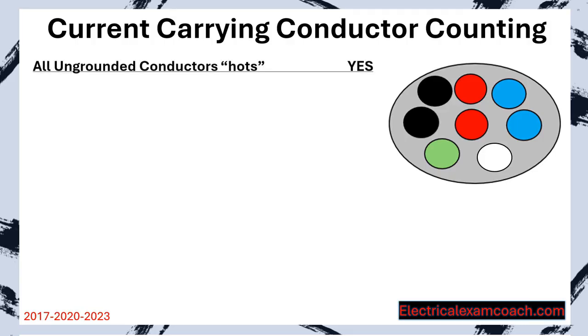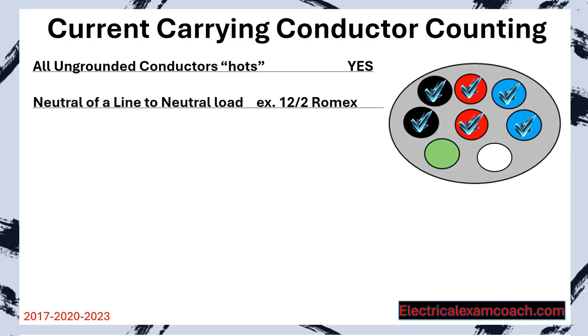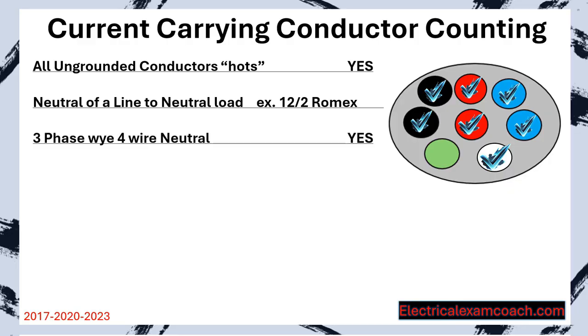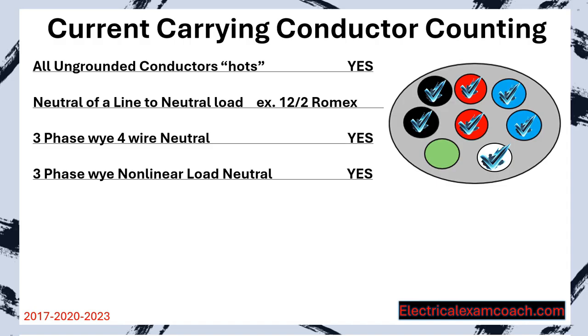The first one's easy: all ungrounded conductors — all of the hots — are going to be considered current carrying conductors under normal circumstances. The second one is the neutral of a line-to-neutral load. If we have a light bulb that draws one amp on a 120-volt circuit, there's going to be one amp going in on the hot and one amp flowing back on the neutral, so it is also a current carrying conductor. Same thing with a three-phase four-wire neutral — we're just going to count it as a current carrying conductor. The three-phase non-linear neutral load from large fluorescent lighting or large computer data centers — you're going to count its neutral as well. Grounding conductors do not count and are not considered current carrying conductors.